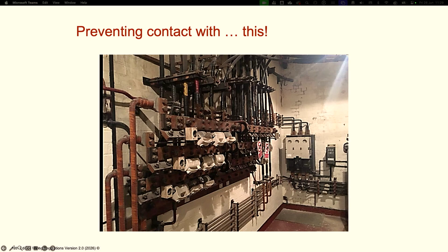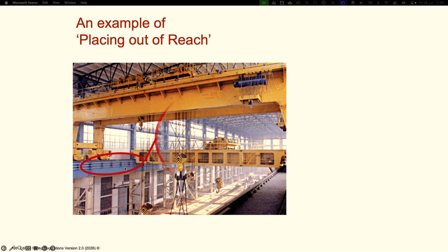You can also do something called placing out of reach. Some people think that's like leaving the front cover off a switchboard a few meters up the wall - that's not what it's there for. If you look at this picture, you'll see this is a crane, called a downshop crane conductor. It picks up very heavy loads but gets its supply from these rails, which are open and bare - you've got 3 phases there.